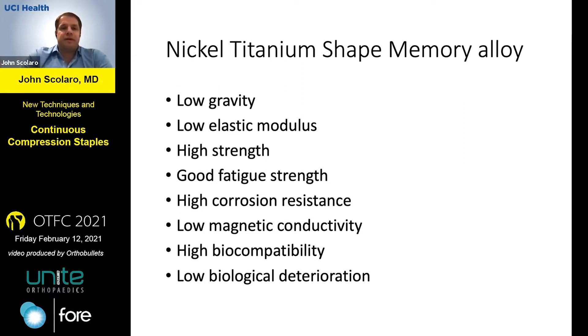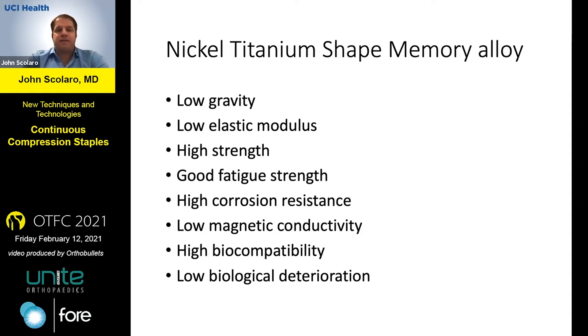Nickel-titanium alloy is actually pretty attractive in terms of biocompatibility for fractures: low elastic modulus, really high strength, incredibly durable in terms of fatigue strength, able to withstand repetitive loading, and high resistance to corrosion. Histologic studies on staples that have been in for a long time show very little wear and very little concerning findings around the interface of the nitinol to the osteocytes.